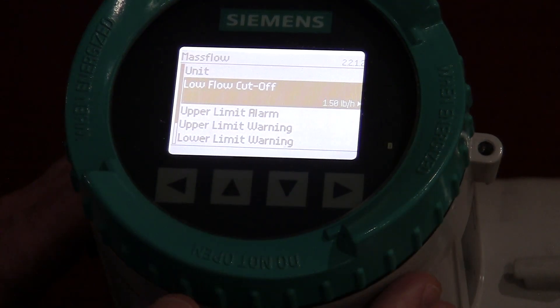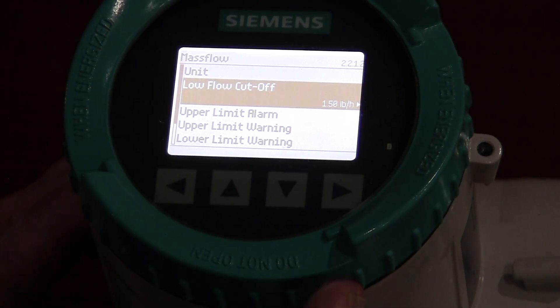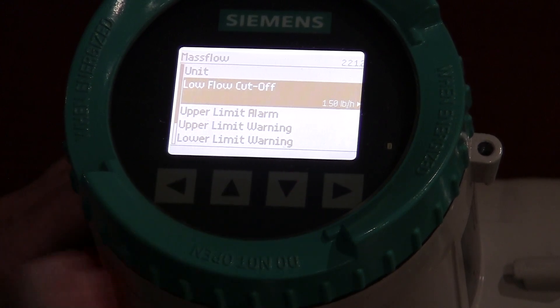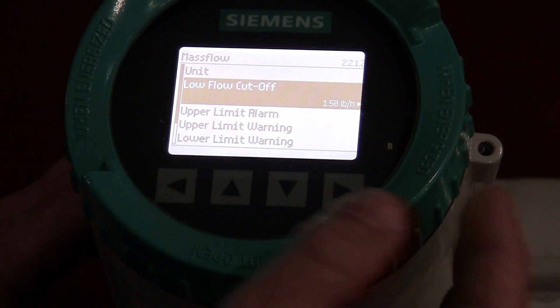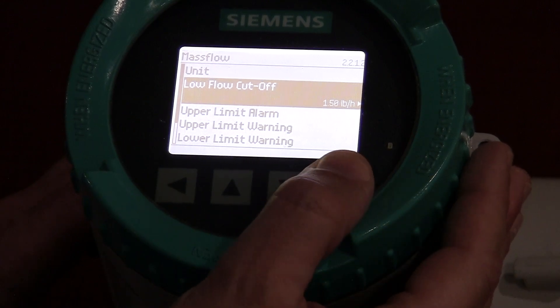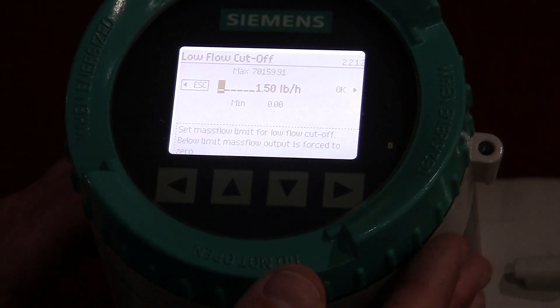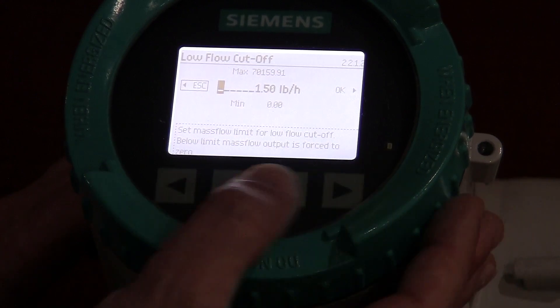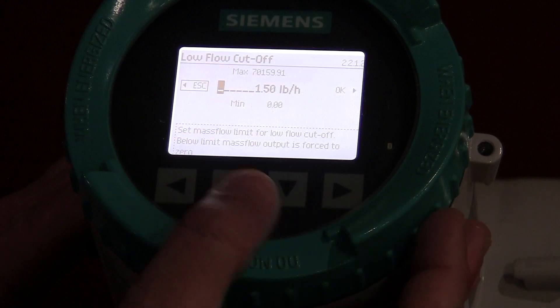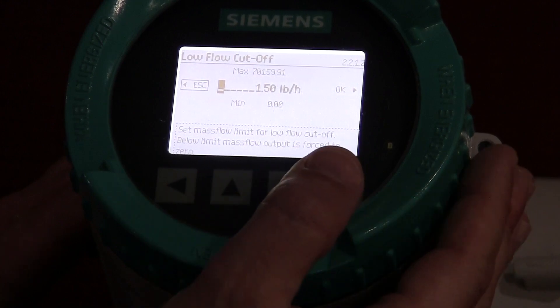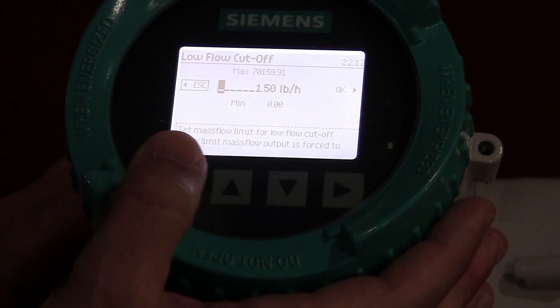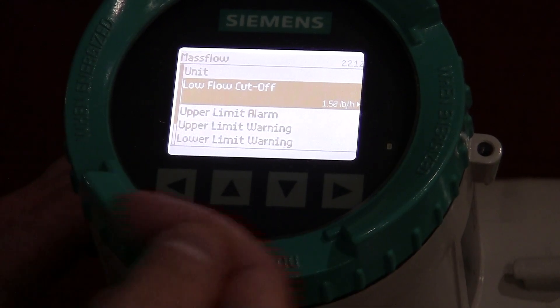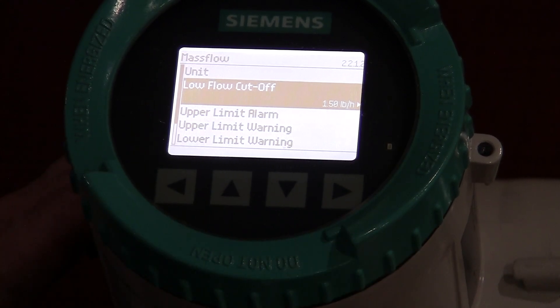The other thing you might want to put in is a low flow cutoff. Sometimes when that flow gets a little bit low, you don't want that meter to be jumping around. You can actually enter a value in there. Right now I have 1.5 pounds per hour as my low flow cutoff. You can edit that just using the left and right arrows and up and down to put that value in. If you hit the back left arrow, that comes back out of the menu.